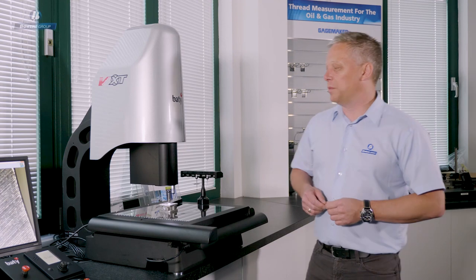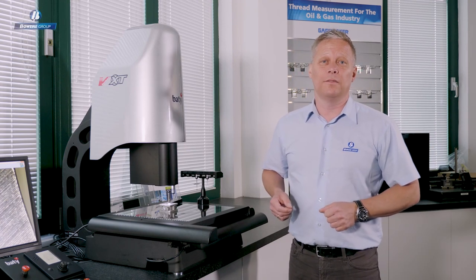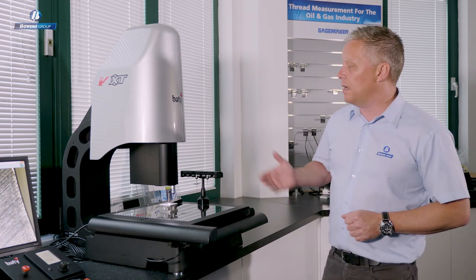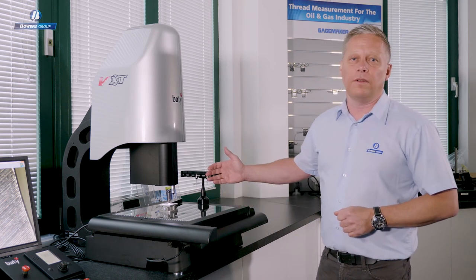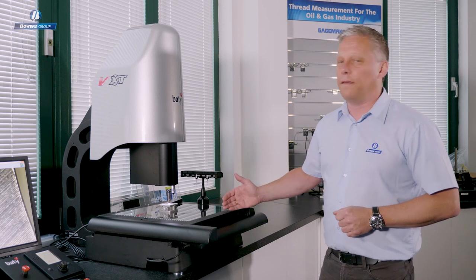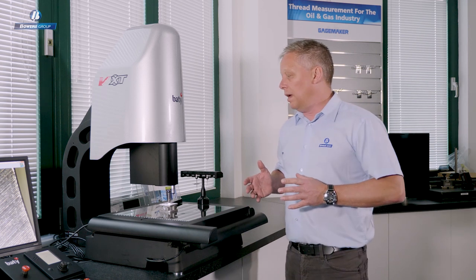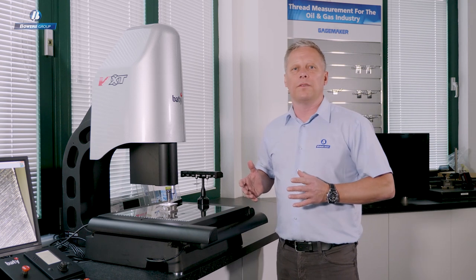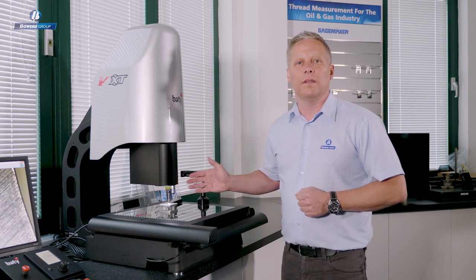Welcome to today's presentation featuring the latest vision system from Baty International — the Venture XT. It is a 300 by 300 XY stage with a full 200 millimetres of measuring range in the Z-axis. It's a 3D system, and the most important point is that this is a vision system and a CMM in the same product.